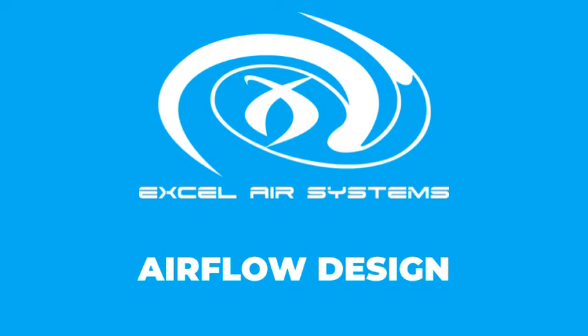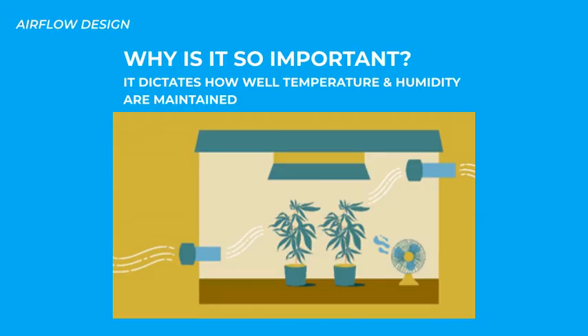Airflow design is probably the most important thing you can do for your room because it's going to dictate how well your temperature and humidity are maintained. And on the air quality side, how that air is coming back, getting filtered and treated with UV. It all comes down to airflow. If you're only able to attack a certain region with one area getting 80% more air than the other, it's only really working in that section. So airflow design is going to make a world of difference.